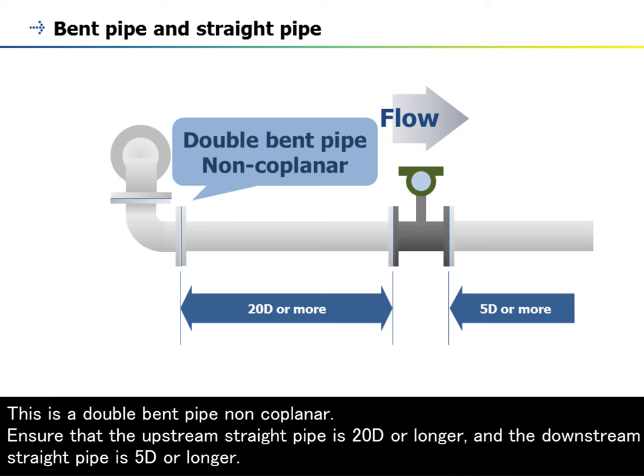Ensure that the upstream straight pipe is 20D or longer, and the downstream straight pipe is 5D or longer.